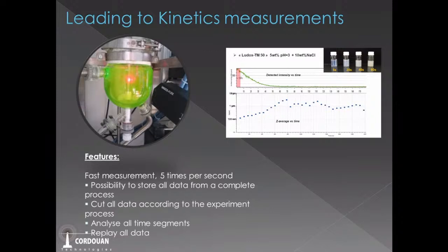You can see on the rear that there is a stirrer inside. You need to stop stirring when you are doing the measurement, because we are looking at the measurement of particles in a Brownian motion. If we put a special movement to these particles, you will not be able to find the good size of particles. So we were obliged to stop stirring, to wait a bit, to make the measurement, and then we start stirring again. You have some parameters that you need to control.